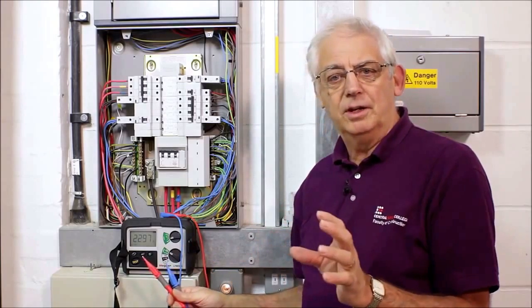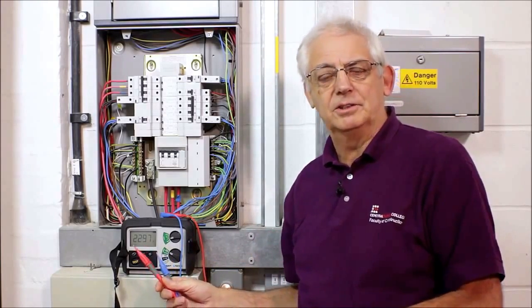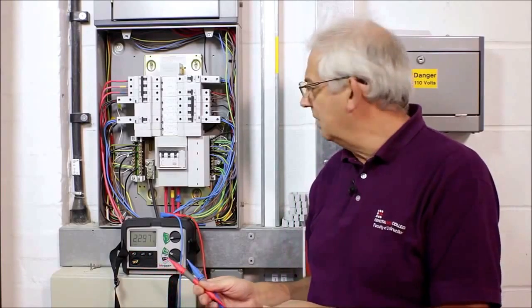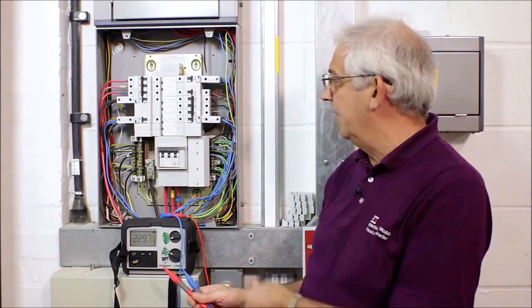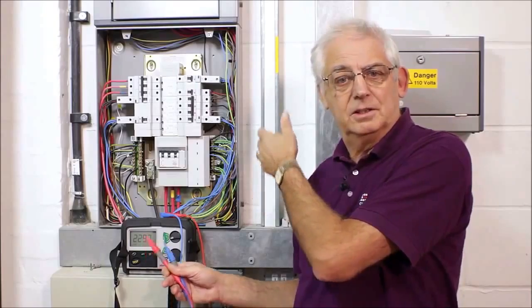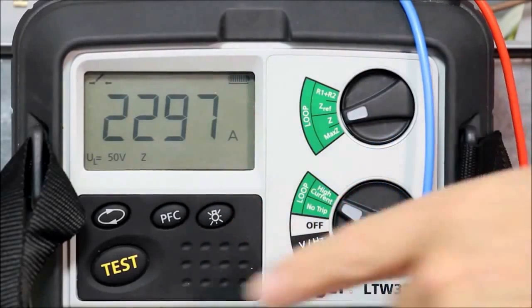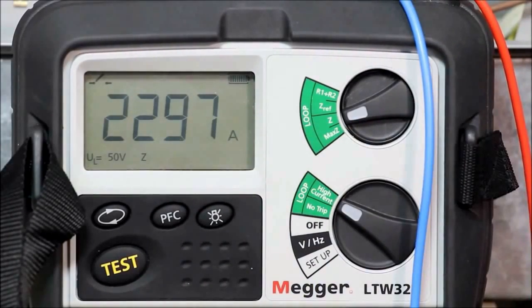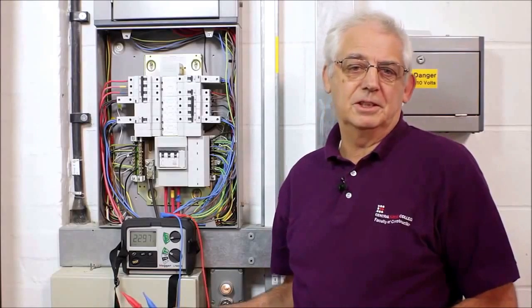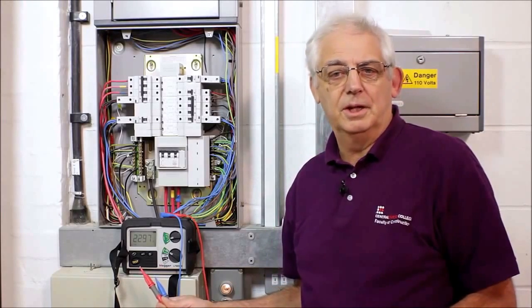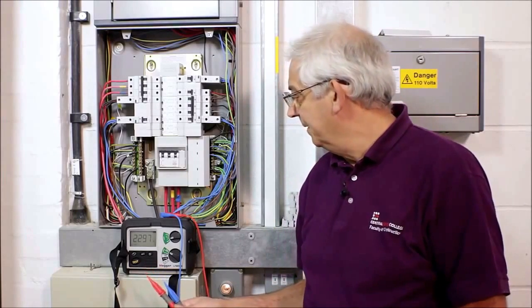And as a rough guide, which is probably as accurate a calculation as you could get, you would need to double the highest value which we had between line, conductors and neutral. So if we say this is 2,300, if we double it, 4,600 would be the value that we would put down for prospective fault current.